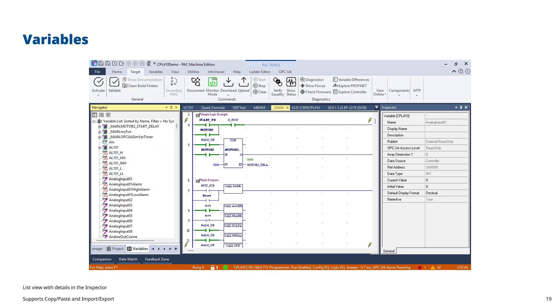And you can also go into the feedback zone, and in the feedback zone there's a reference tab. If I select analog input 01 and then go to the reference tab in the feedback zone, it will tell me everywhere throughout the logic where that input 01 is used. And then I could double click on the reference area in the feedback zone, and it would open up that subroutine or that reference location where the analog input 01 value is used. So very good for fault finding, because you can start at the end, the output, and work back to see what interlock is maybe stopping the output from operating. Or you can do it the other way. You could start on an input and then move forward to, again, find out what interlock or what other function is not working and why your process isn't running as you expect it to.